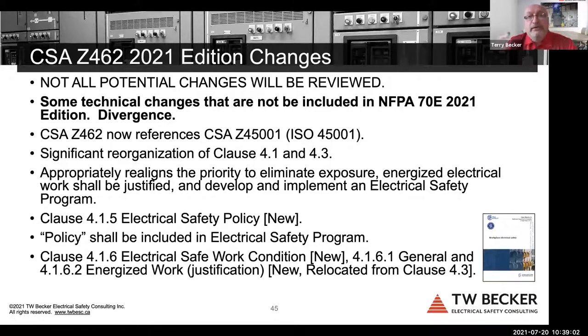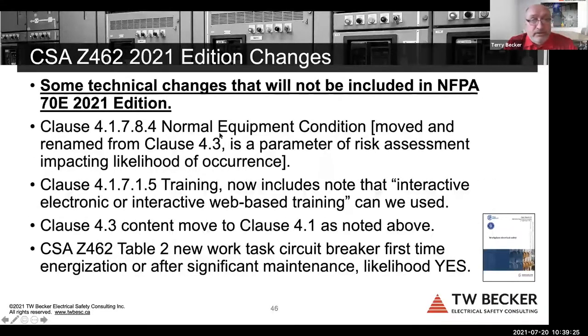And then it moves into the electrical safety program clause, and the clause numbers have been renumbered to accommodate this. You've got to realize the clause numbers will change for some of the clauses in clause 4.1 and some of the clauses and articles in Article 130 or clause 4.3. So if you were quoting a clause number before, it may be different now in the areas where the structural change occurred. And one of the things I said is we kept the word, changed it to normal equipment condition instead of normal operating condition, but we put the 6 items under risk assessment where, in my opinion, it should be. In 70E, it's floating outside of the risk assessment procedure.